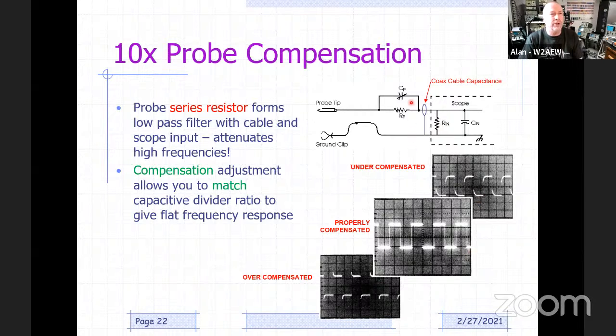Okay, so you plug the probe in, and you look at that square wave, and then you simply adjust that compensation adjustment, a little screwdriver adjustment on the probe, until the square wave looks good. And what you've done then is given a nice flat frequency response of the probe, so that you can now believe the amplitudes that you see of the signals that are 10 or 20 kilohertz or higher using that probe.